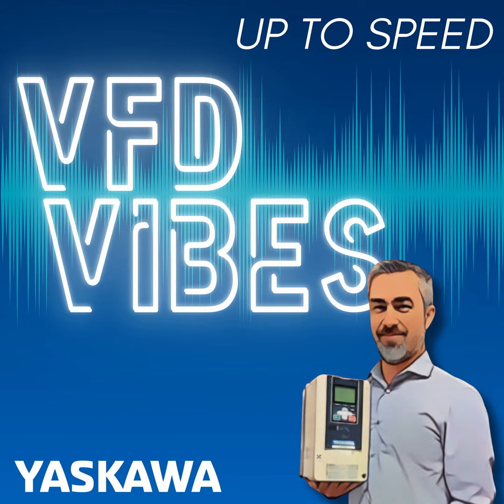And what tool do we have to help with that? Well, we have our Harmonics Estimator, and the Harmonics Estimator allows you to estimate harmonics at the point of common coupling. Our tool's very easy to use. You don't have to be an electrical engineer to use it. Basically, we have our Yaskawa drives loaded into the tool, and you put in what your power source is, what kind of transformer, what's the capacity of the transformer feeding it.